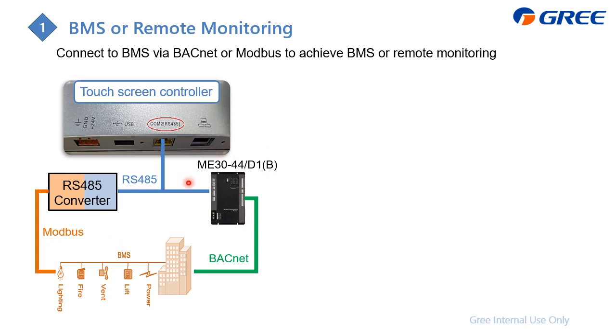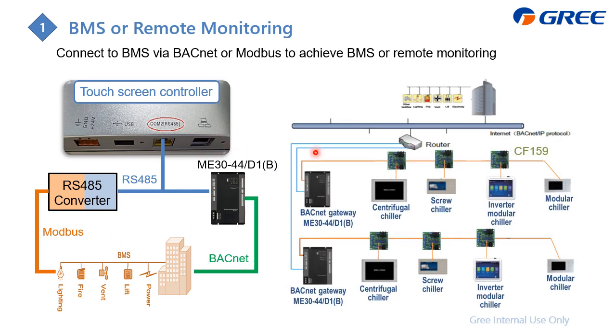And not only for the centrifugal chiller, but for all our Gree products. From this picture you can find that just by relying on this gateway, this ME30, you can connect to the centrifugal chiller, or the screw chiller, or even the modular chiller. This is actually RS485, and just use this CF159 device. They can be combined together, and then go to this gateway, then from this gateway to this router, then to the computer, which is the BMS system. So what I mean is you can use this device to control all Gree chillers.